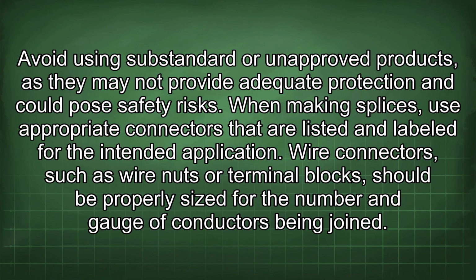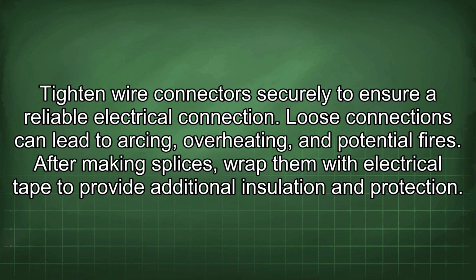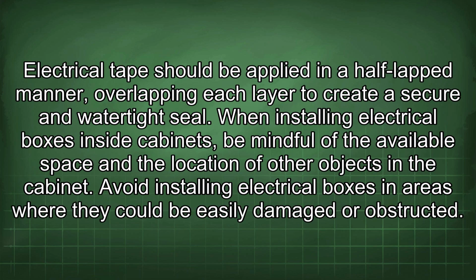When making splices, use appropriate connectors that are listed and labeled for the intended application. Wire connectors, such as wire nuts or terminal blocks, should be properly sized for the number and gauge of conductors being joined. Tighten wire connectors securely to ensure a reliable electrical connection. Loose connections can lead to arcing, overheating, and potential fires. After making splices, wrap them with electrical tape to provide additional insulation and protection. Electrical tape should be applied in a half-lapped manner, overlapping each layer to create a secure and watertight seal.